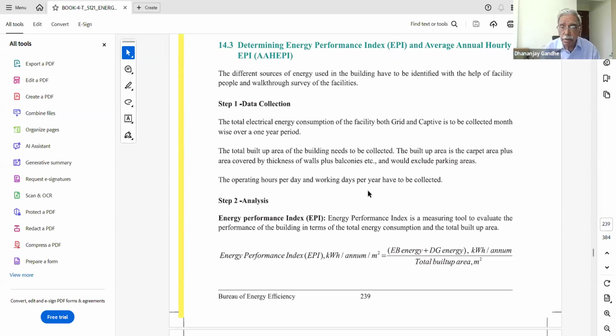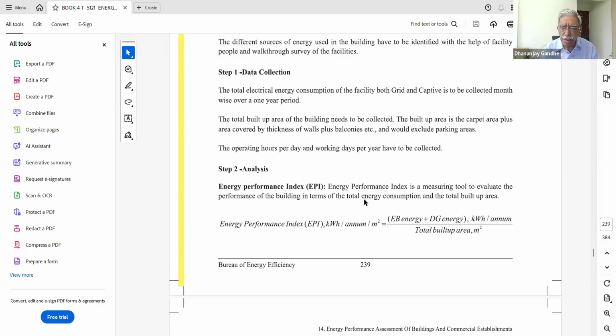It becomes an exercise. Architects usually will give you the built up area. This calculation gives you the energy performance index, EPI, and then EPI can be compared with the standard values. It can be compared every year with its own value to know how the building's energy consumption is changing year after year, whether there are improvements, whether it is reducing or not. And it can also be compared with similar buildings, of similar size and similar consumption, to find out whether our building is comparatively efficient or not.